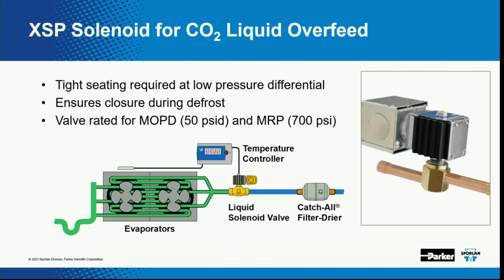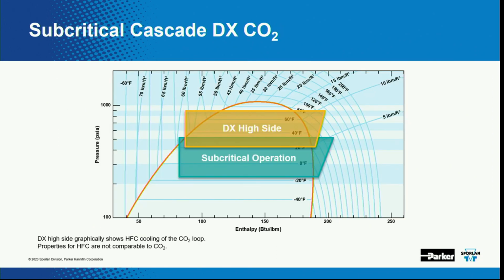Worth noting that this is the solenoid valve that we deploy for these applications. This is our XSP. Its claim to fame is its tight seating at low pressure differential, whereas the others not so much. So you'll probably see these out there, ensuring closures during defrost. That's the solenoid for that application. That's not our pulse width valve, and it's not one of our standard solenoid valves that we would use for just a liquid shutoff or liquid line solenoid.